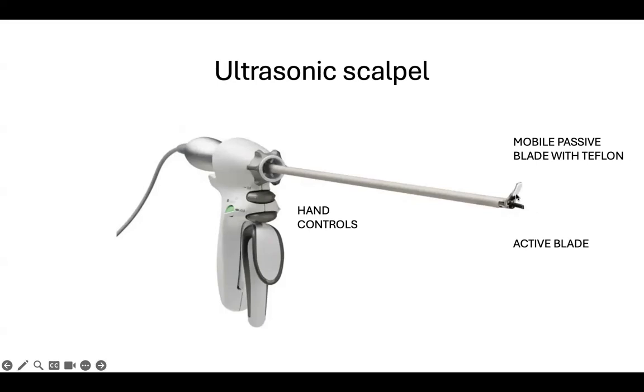So when the tissue is kept here and this rubbing action happens against the passive blade, it is creating friction, which then gets converted into heat, and that heat is going to coagulate or seal the tissue or vessel, whatever is in between. The principle is, the more pressure you apply, the more it is going to crush the tissue and cut it prematurely. And if you apply lesser pressure, no amount of sealing is going to happen, because a moderate amount of friction has to be generated for the sealing to happen.